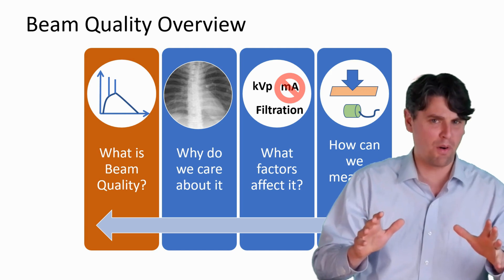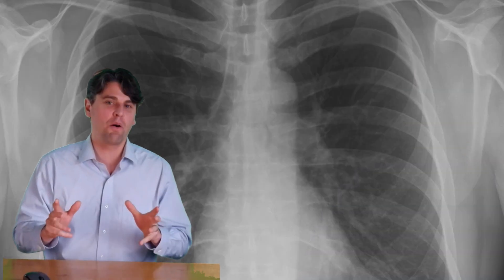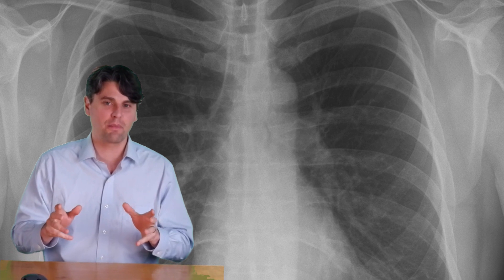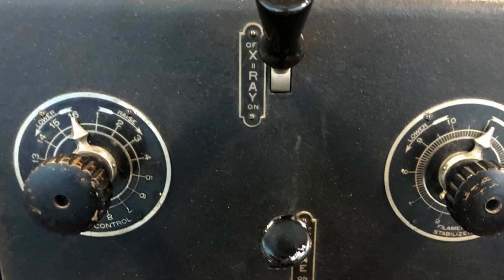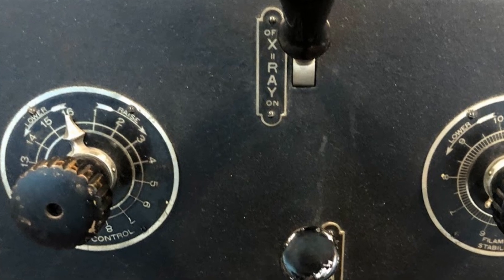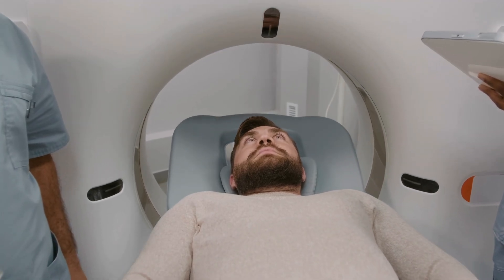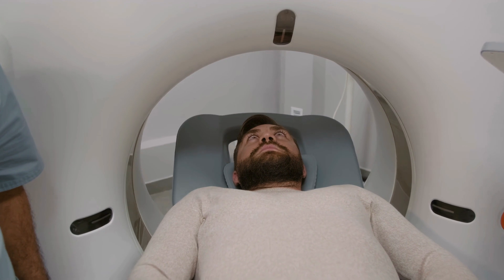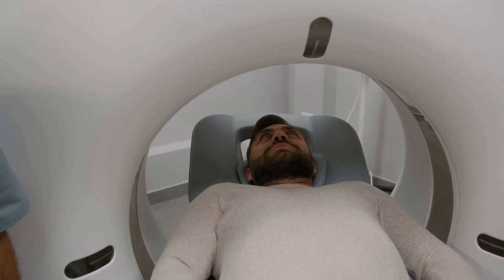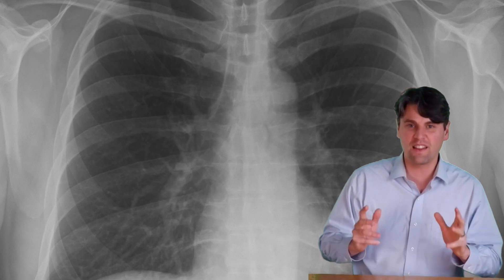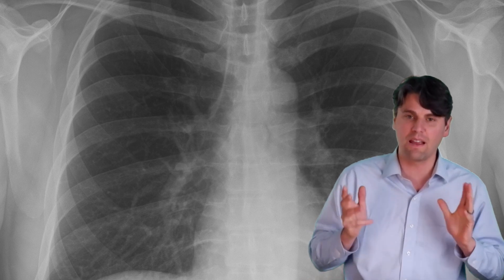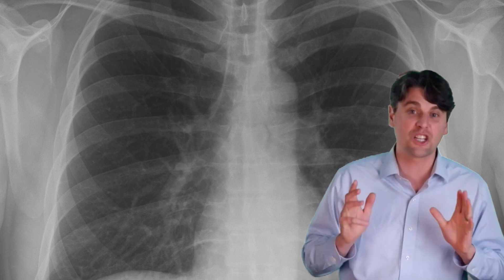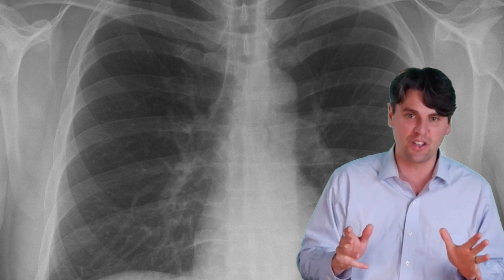First, we're going to talk about what is beam quality. Quality is actually how we describe the x-ray spectrum. It's just saying that the x-ray beam coming out from one setting and a different setting actually have a different quality. So that means they're going to pass through the patient differently. Specifically, the things that we talk about most are the x-ray spectra. So saying beam quality means that the shape of the x-ray spectra is changing.